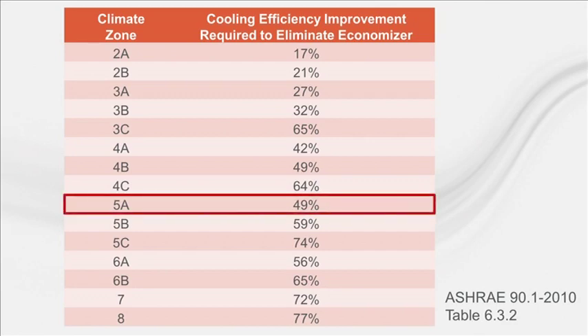For example, in climate zone 5A, which includes the northern halves of Illinois, Indiana, and Ohio, the IEER of the VRF system would need to be 49% higher than the minimum required IEER in order for the economizer to be eliminated. Today, most VRF manufacturers offer products that can meet these elevated IEER thresholds. So even if an indoor VRF unit exceeds 4.5 tons, you can still be exempt from the economizer requirement by installing higher efficiency equipment.